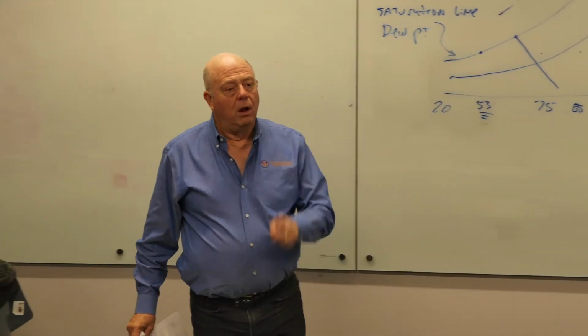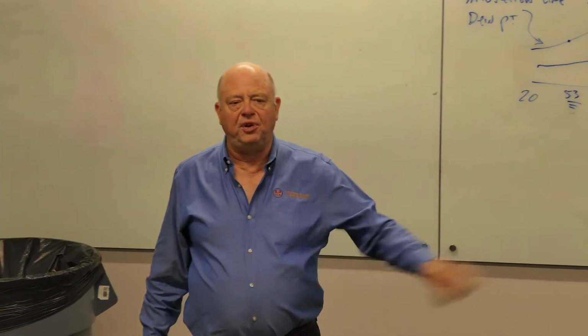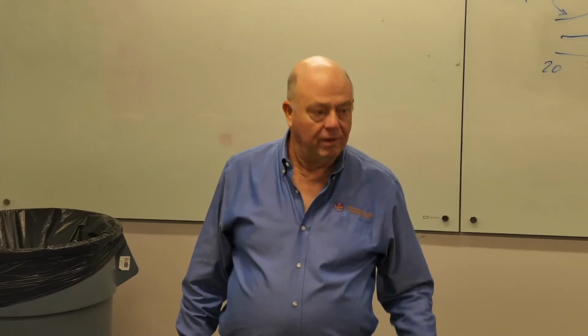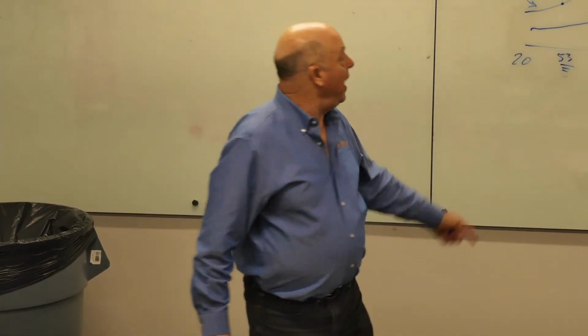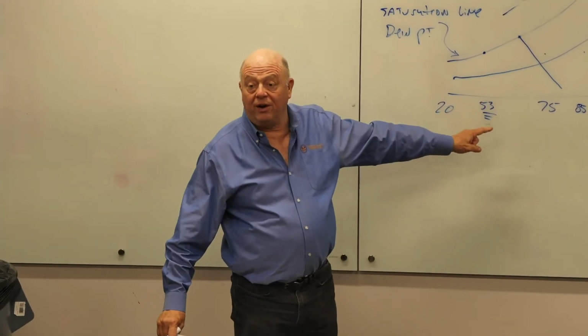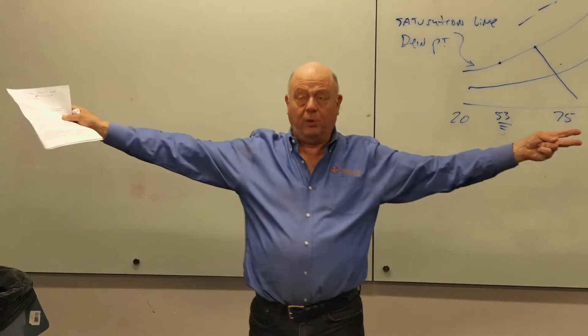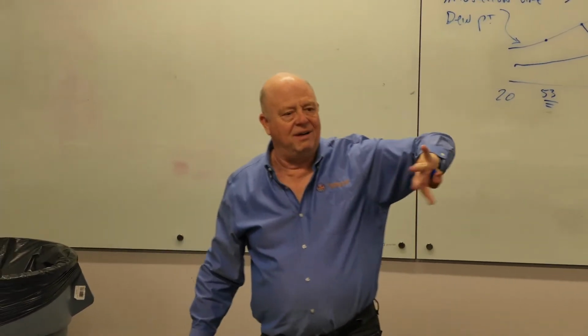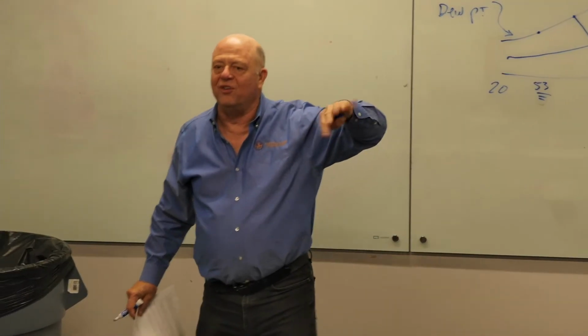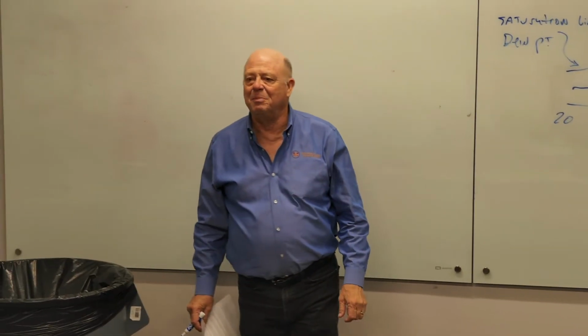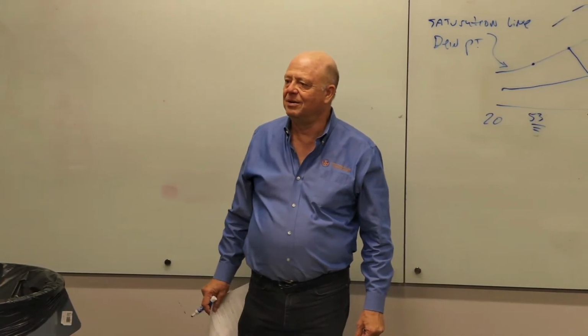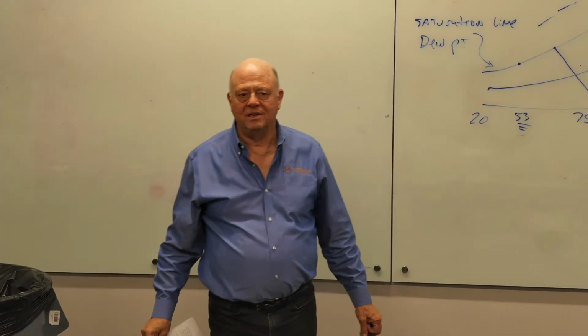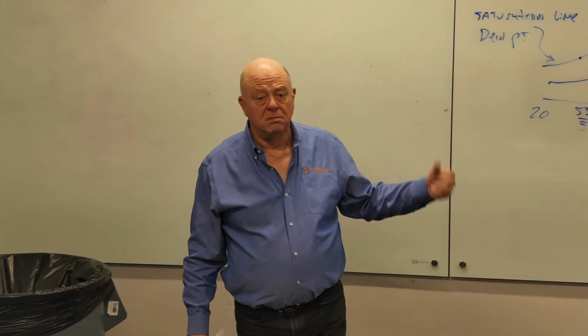What if we were making 50-degree air? Yes, now it will. And if we were making 53-degree air in a duct in a 53-degree dew point room, we'd probably have just a little bit starting to show, a little bit of dew on the outside of the duct. This assuming it's not insulated, right? Or a pipe. You get into this a lot with pipes.